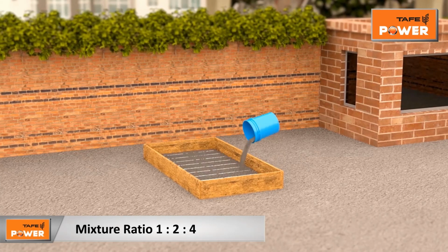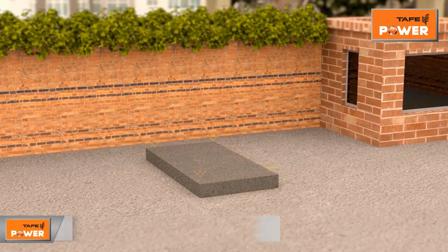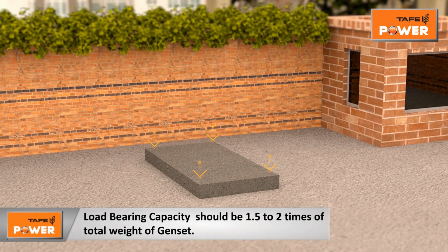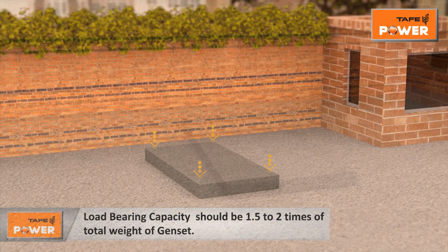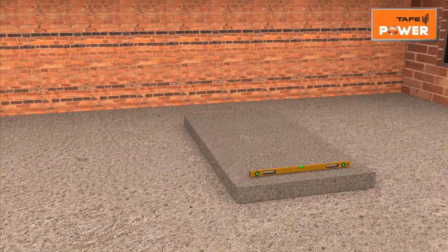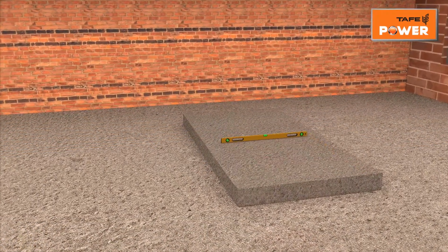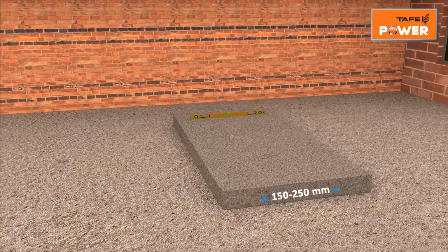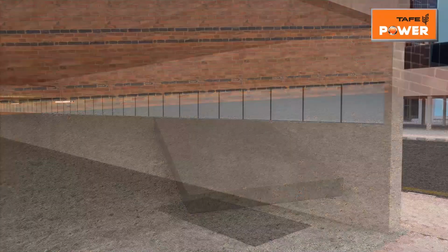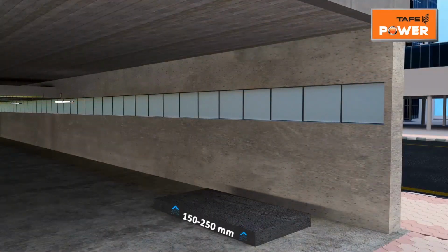Prepare RCC foundation by using same mixture of cement, gravel and sand. Genset foundation should be strong enough to support 1.5 to 2 times of total weight of genset. Foundation should be water leveled and evenly flat. Foundation should be 150 to 250 mm above the ground level.